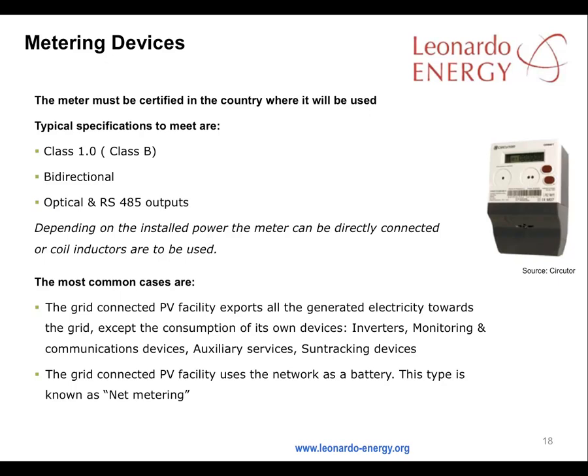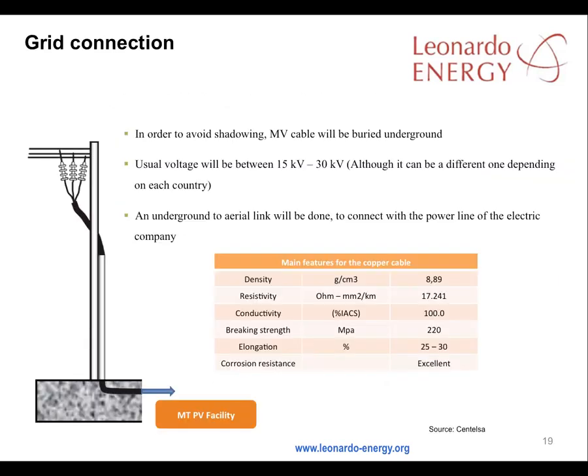Or a net metering setup where a grid-connected PV facility uses the grid as its battery. For grid connection, in order to avoid shadowing, medium voltage cables should be buried underground rather than carried above the modules. 15kV to 30kV cabling is commonly used, although that can vary in different countries.